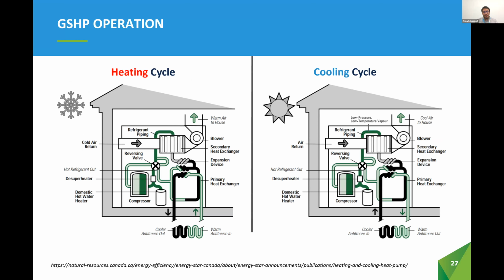Now, we would be remiss not to mention ground source heat pumps, as they are a great alternative technology which address many of the shortcomings of air source heat pumps. Their operation is very similar to what we've just reviewed, except the heat is exchanged with the ground rather than ambient air. Due to the relatively stable temperature of the Earth below the frost line, ground source heat pumps are extremely efficient and reliable, and do not require a supplemental heat source when sized for the full heating load.